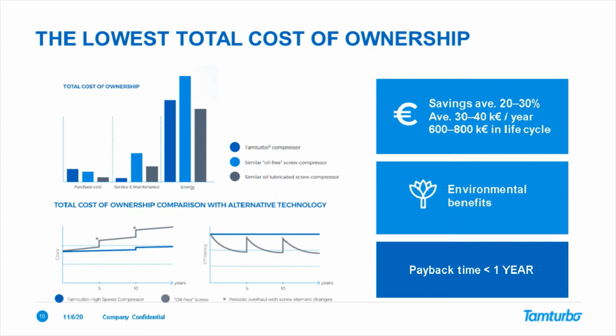oil-free screw. But what needs to be noted is that even if you would get the oil-free screw compressor for free, you shouldn't take it, because you lose more on the service and maintenance and energy than whatever differences on the purchase cost. And if you can, because of the better energy recovery, utilize the heat, then you can discount that whole energy bar from our solution, which is the typical case. In many places this is the first compressor where the energy is actually taken into use. In most other compressors, it is blown to the sky with a cooling tower or dry cooler.